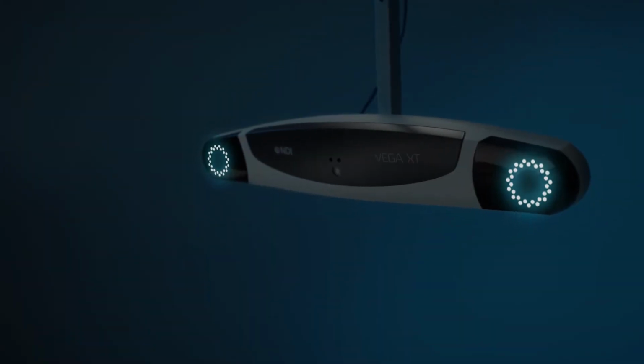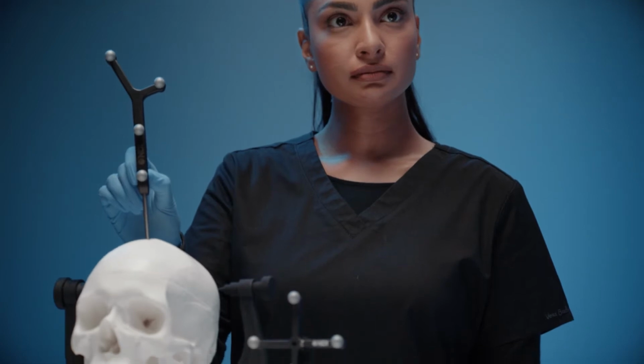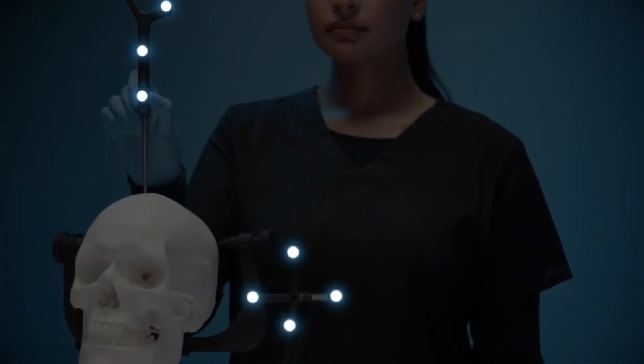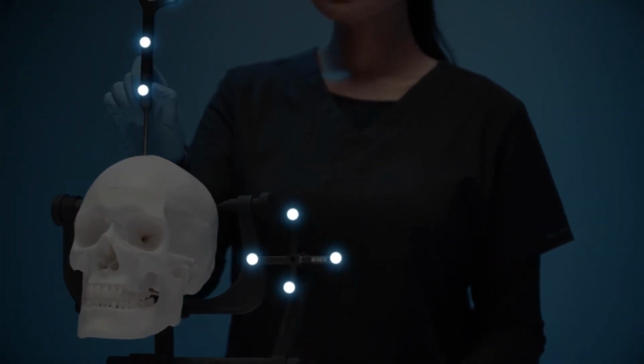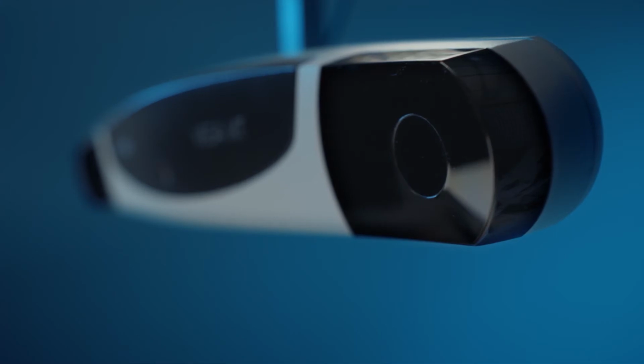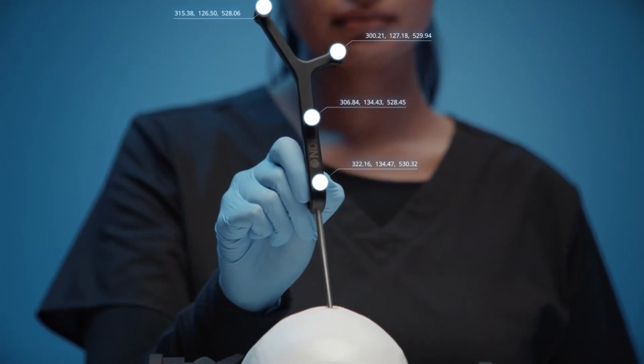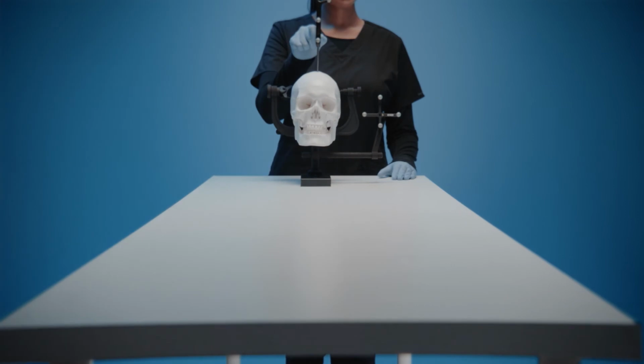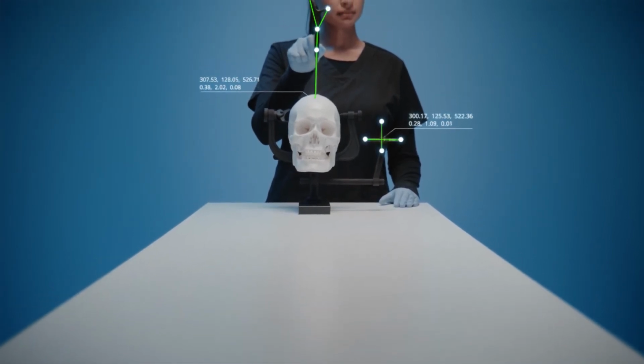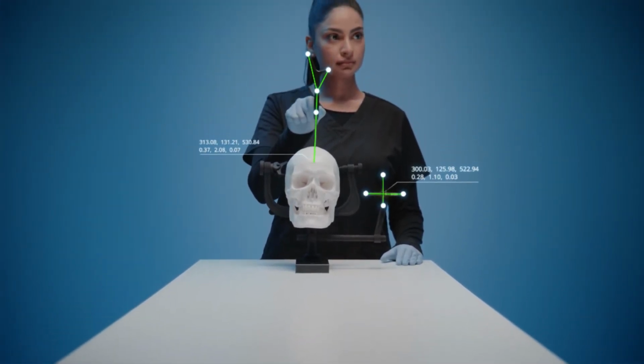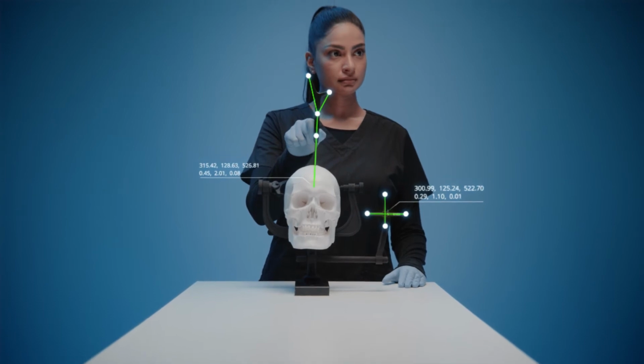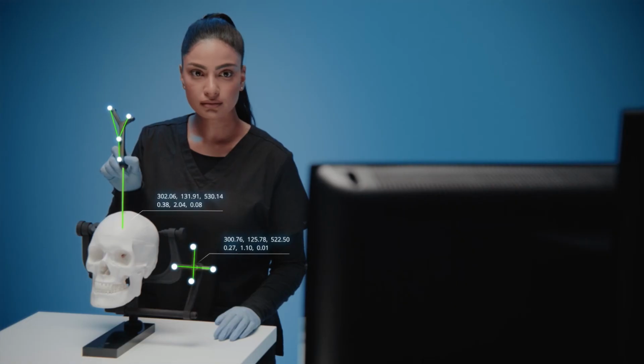The tracker floods the measurement volume with infrared light to illuminate the markers. This light is reflected to infrared sensors on the tracker, which triangulates the marker's coordinates. These coordinates are mapped to a specific instrument, and its transformations are calculated, determining the position and orientation.